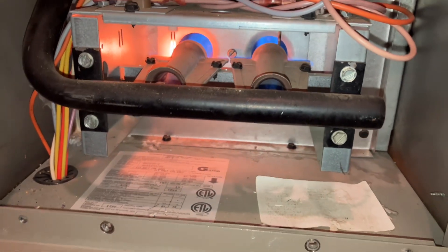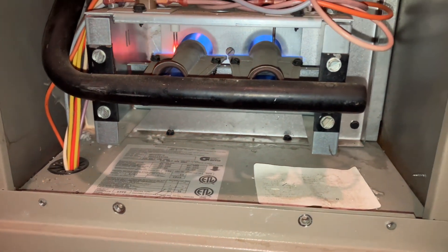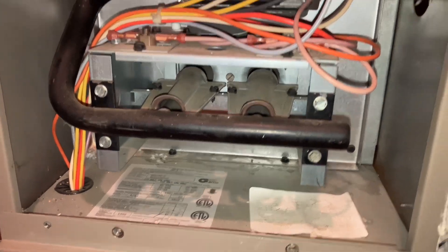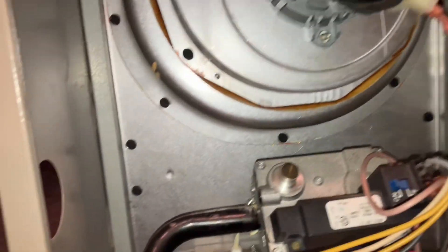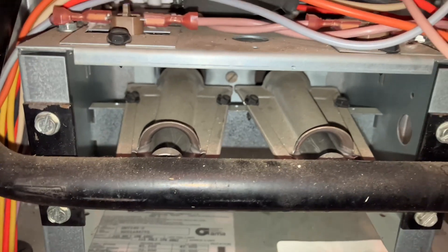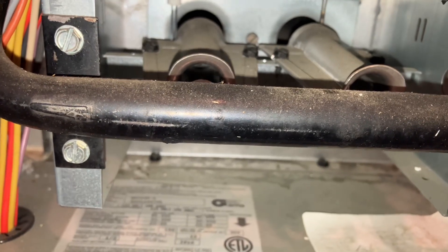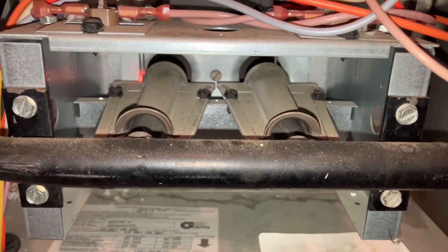I just got this call. The flame keeps dropping out. See if we got any codes. That looks like it's normal operation — the heartbeat. So it could be that flame sensor. We'll let it ignite again.